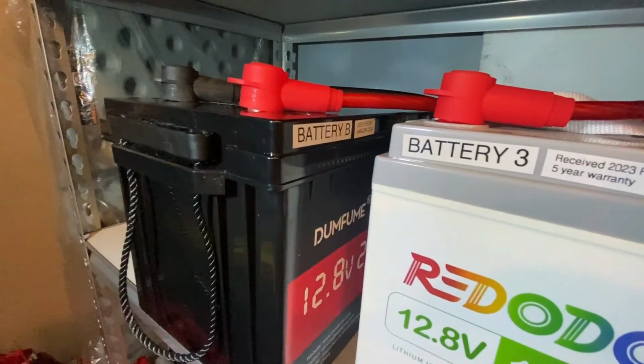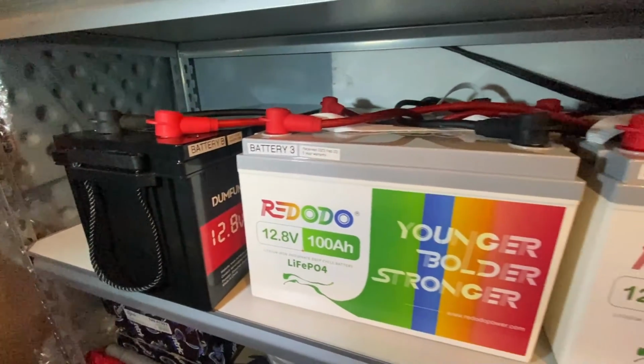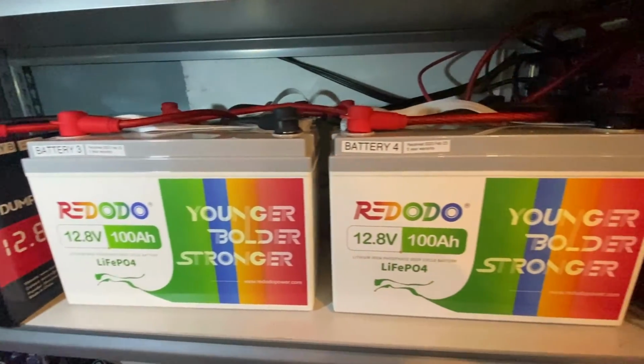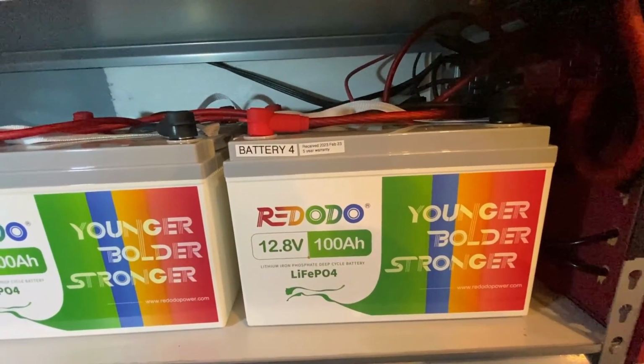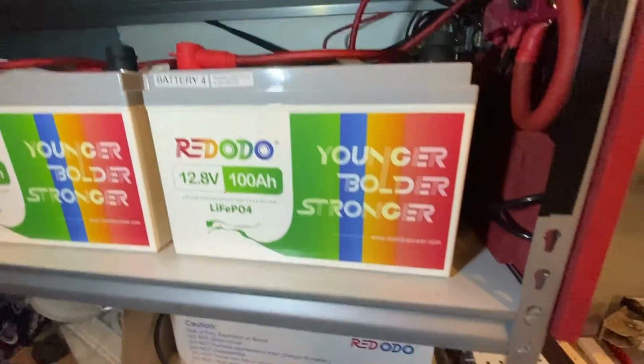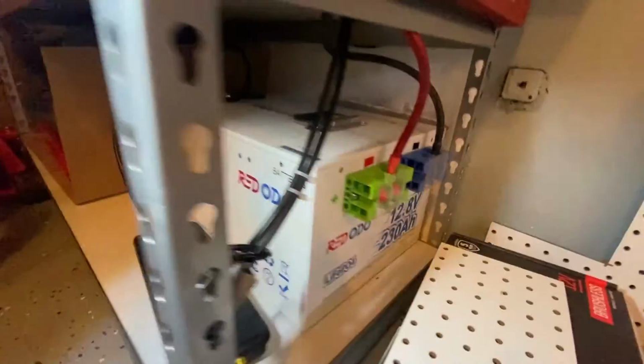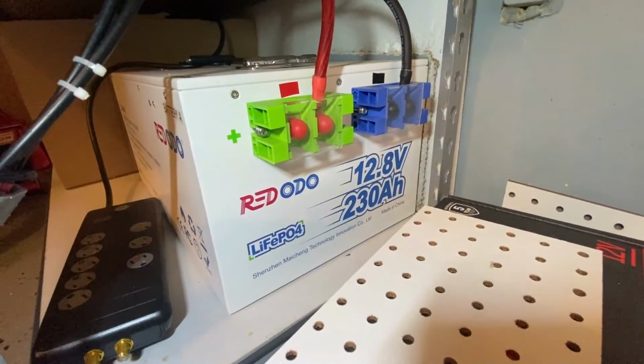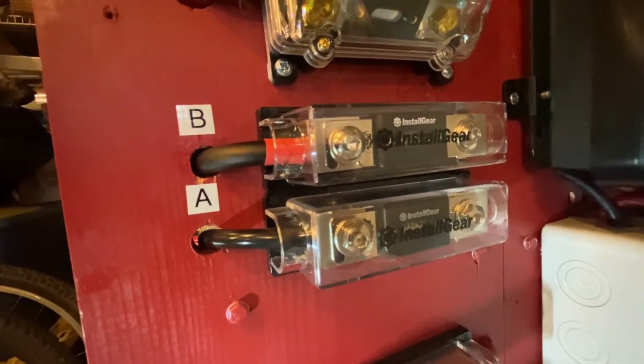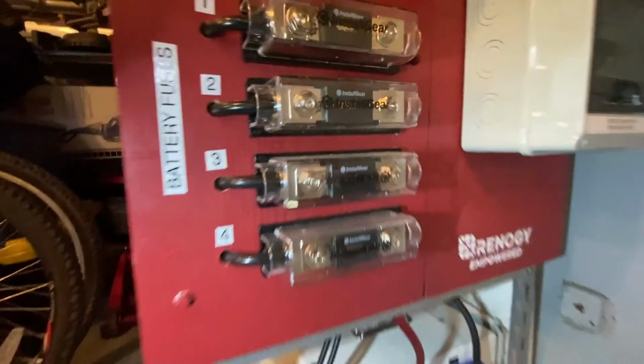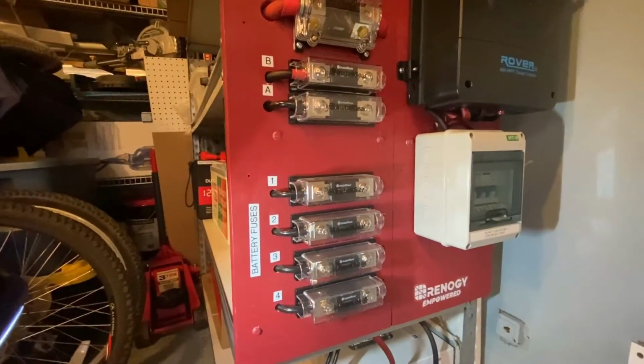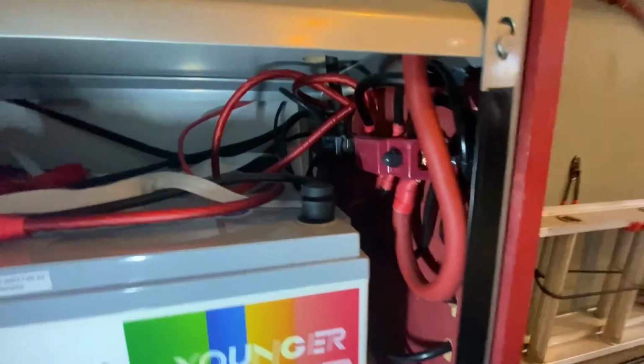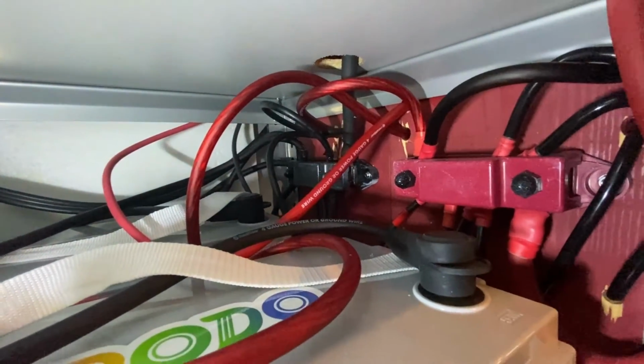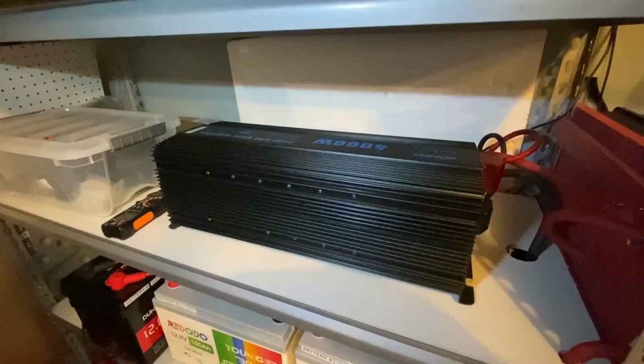Here is another view of the system after connecting the new battery. All the batteries are connected to two bus bars through fuses on the positive side. So this fuse B is for the new 200 amp hour battery, fuse A is for that 230 amp hour battery, and the other 4 fuses are for 100 amp hour batteries. Here is a better view of the bus bars again in the back.